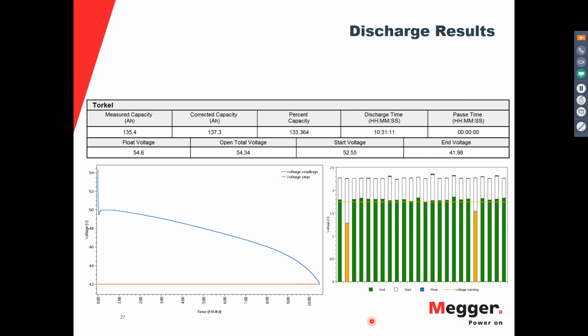Basically, you get the numeric values of the voltages: the float voltage, open total voltage, start voltage, and the end voltage, which is very important. Remember, you do not want to damage the battery by going below the end voltage recommended by the manufacturer. And of course, you get your measured capacity, the corrected capacity, and the corrected percentage capacity. You can also see the total duration of the discharge and any pause time. If the test was interrupted or there was any pause during the test, it will show there, and you will see that also in the graph. We have some examples, or one example, later on.